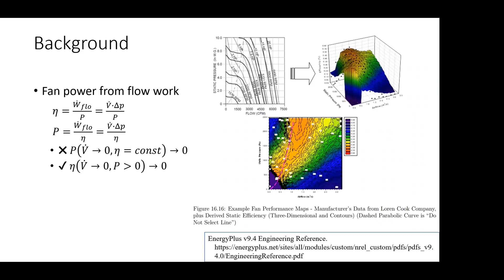This is especially important when we have a scenario with a low flow rate, but the fan is controlled to maintain a certain level of pressure, which is very typical for VAV systems.